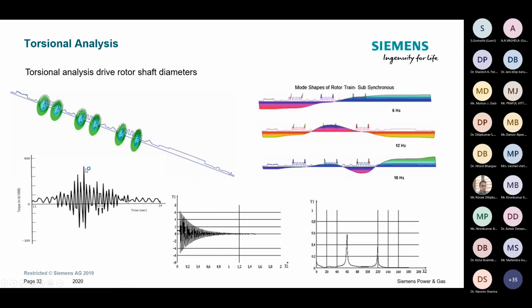Normally that happens in a few accidental events where the torque is almost 7 or 8 times the nominal torque, and that happens in a very narrow time frame, let's say 0.2 or 0.3 seconds. If your shaft is not designed to sustain that load, then it will break into two pieces, and that has happened in the past. In old designs we see the rotor break in two pieces.